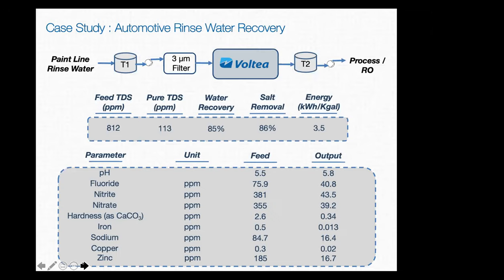So very simple system. You had tank one, which was picking up the rinse water, goes through a 3-micron filter to take out any particulates, through the Voltea system, dropping that TDS from 800, which was their blowdown or overflow limit, down to around 100, and then back into tank two, and then back into either their process, back into the tank, or to another process such as a cooling tower or a reverse osmosis system, where they could then reuse that pretty high quality water.